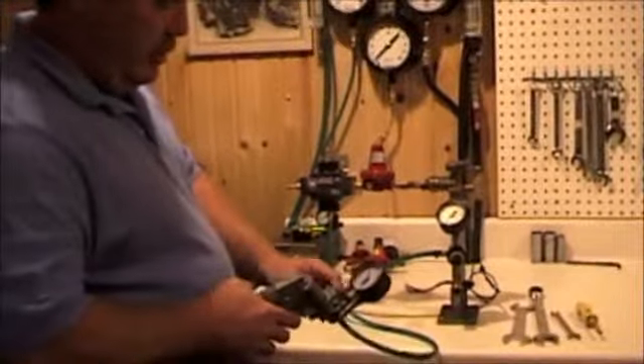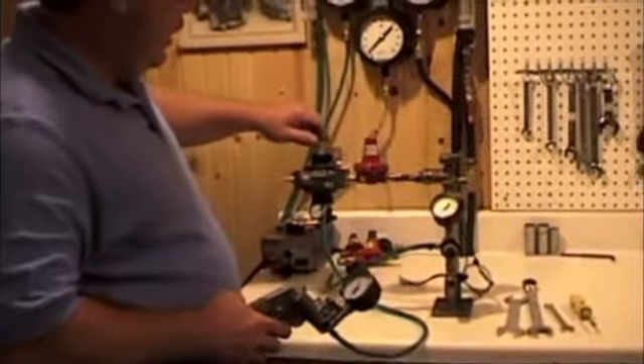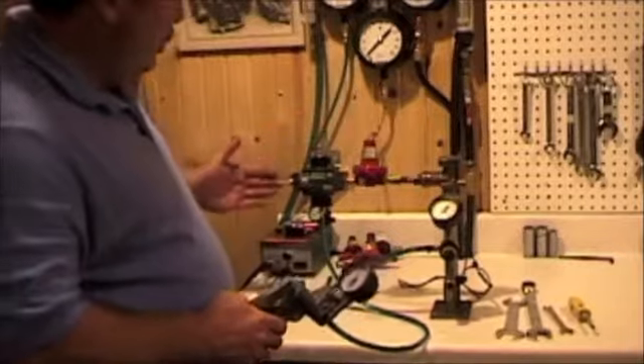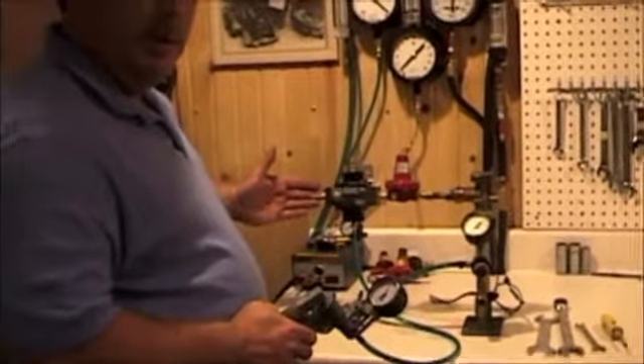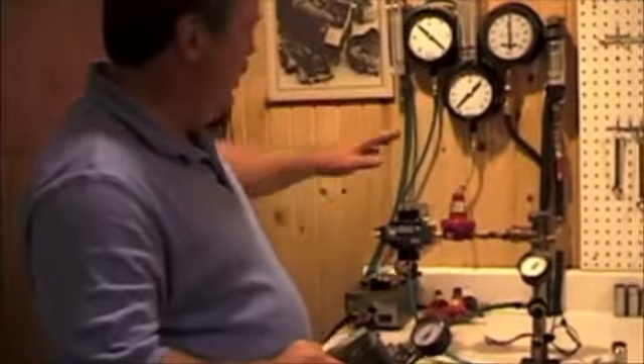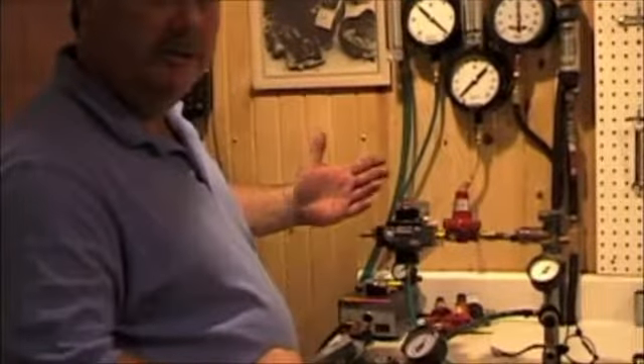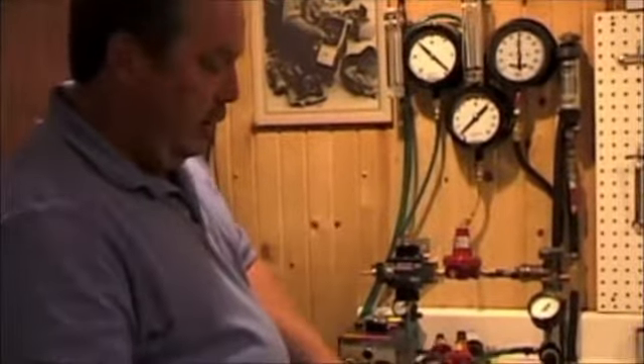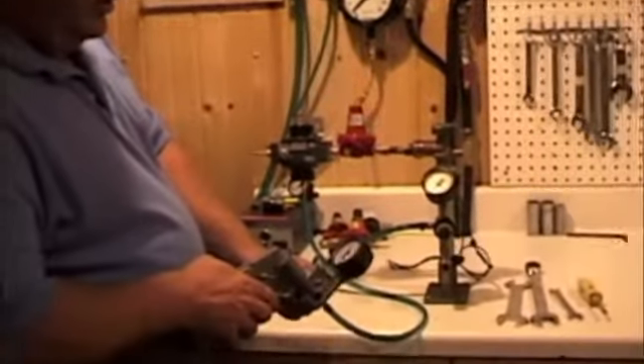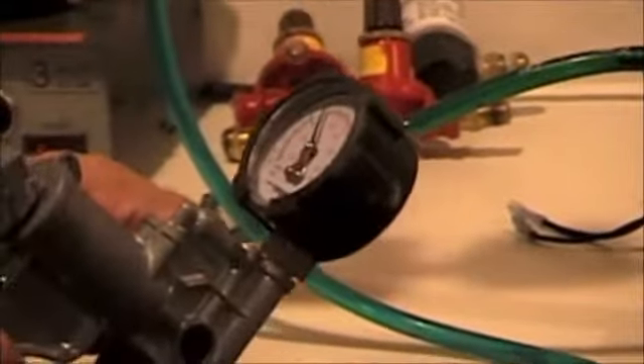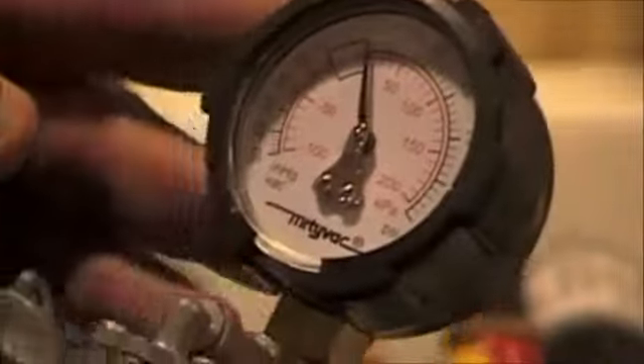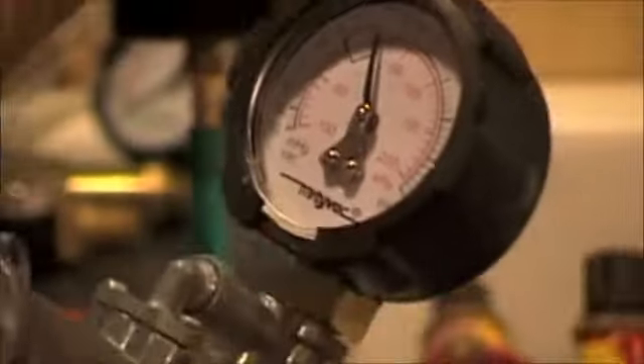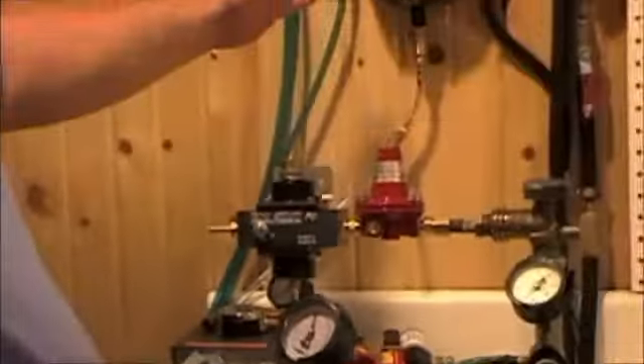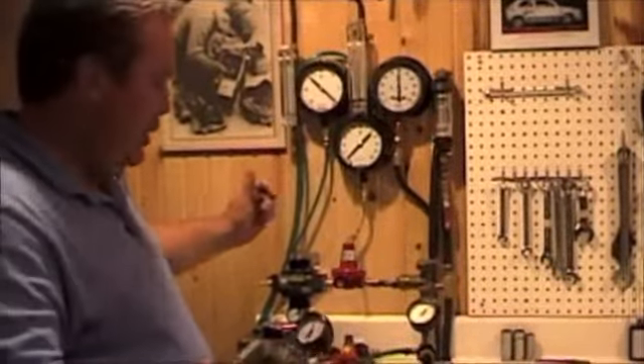So we'll turn on our air, and at this point we have no pressure at all on it. And if I start to increase pressure, you can probably hear the propane starting to run at this area. I have the calibrating line off of it so I can hear what we call our start time. Right now this unit has about a 2 pound of pressure start time. 2 pounds of pressure, and I'm going to set this up on another gauge other than using this hand one so you people can also see what we're seeing for pressure.